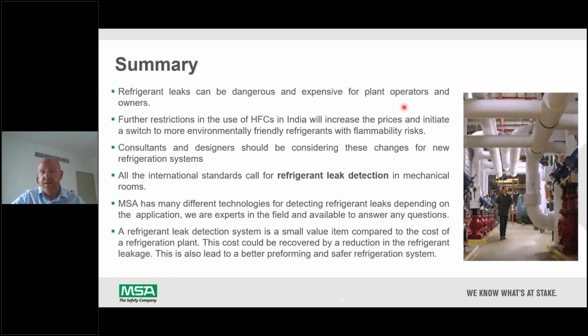So consultants and designers should be looking at the evolution of gases and considering these changes for new refrigeration systems, because refrigeration systems now last 20, 25 years. What happens is the gases may not be available in another 10, 15 years. So they should make the system with a new gas, or be able to switch to a new refrigerant. All of the international standards call for some form of refrigerant leak detection in the mechanical rooms, at least.